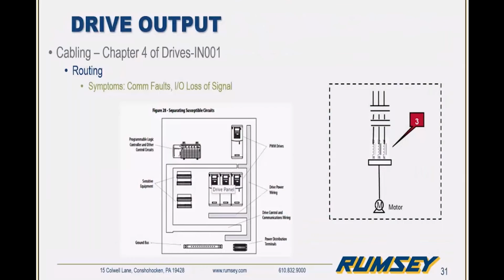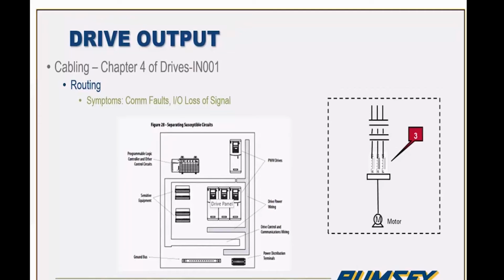So another thing to consider, as far as the output of the drive and inside the panel, and it's very frustrating if it's ever occurred to you, is intermittent comm faults and I/O loss of signal. These can occur when we don't properly route the power output cable or keep the drive components or power components separated from our sensitive equipment. The diagram here at the bottom shows all of the power components, the drives, and their power cabling routed on the far right-hand side of the enclosure and kept away from any of the sensitive equipment and the control wiring. Again, we want to do that whenever possible to keep from inducing any of the noise created by the drives into the rest of the equipment and our control signals.